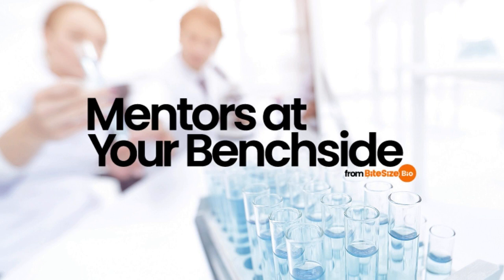And then work out the range of values and see if it is within the acceptable margin of error. If it is, great. If not, it might be time to calibrate your scales. The other test you can do is the pan position error test. Now your scales should be able to weigh your sample accurately, even if you've placed the sample off-center. To test this, note the weight value given when your sample is placed in different positions on the scale's pan.